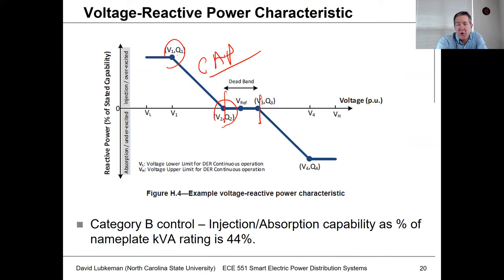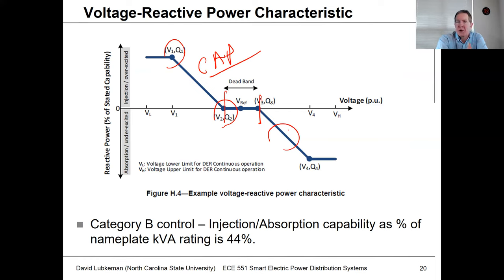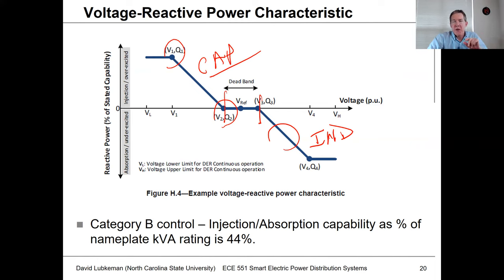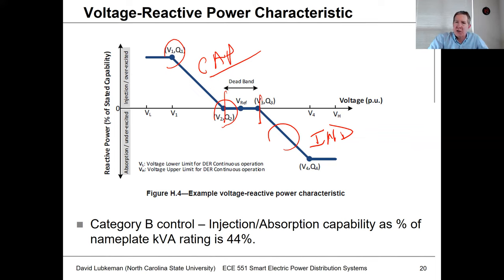On the other end, if the voltage goes up too high, you actually start to inject negative reactive power — you can think of the device as absorbing reactive power. The passive element that absorbs reactive power is an inductor, so it's almost like we're putting an inductor in there to drop the voltage down. Real power injection boosts voltage up, but if these devices also absorb reactive power, it tends to drag the voltage back down again. You can actually adjust these devices so the voltage boost caused by real power is offset by reactive power flow. However, if you don't do this correctly, it could interact improperly with the utility voltage regulation, so this all has to be coordinated with the utility.